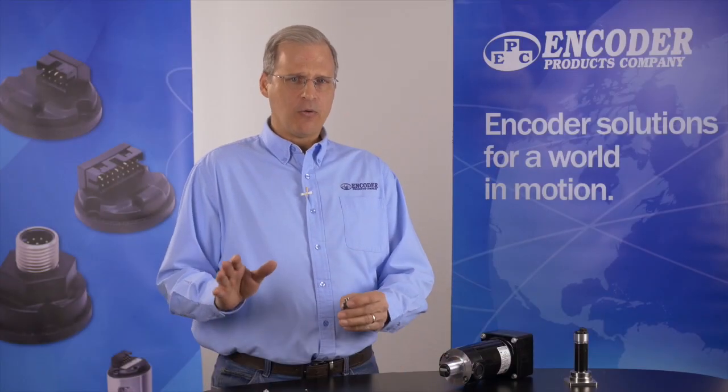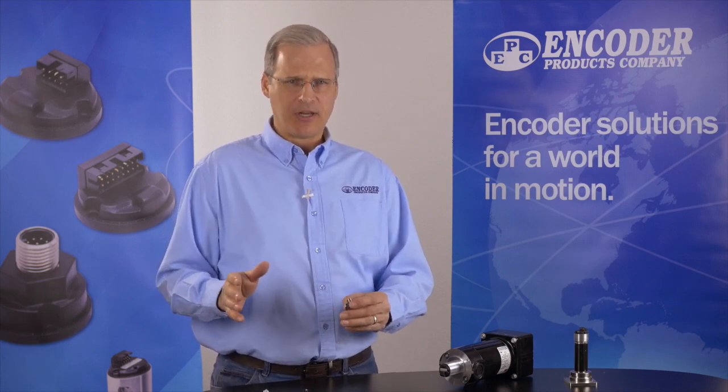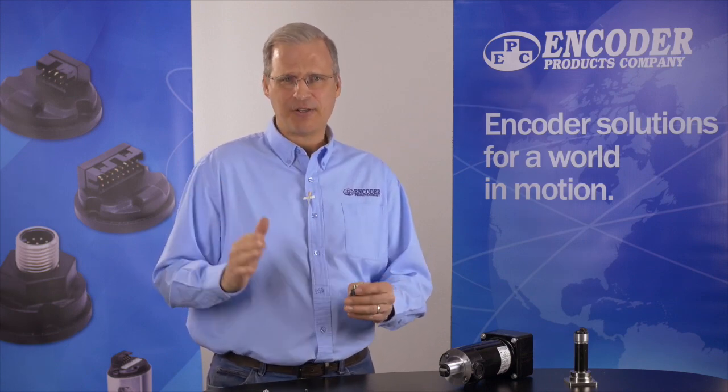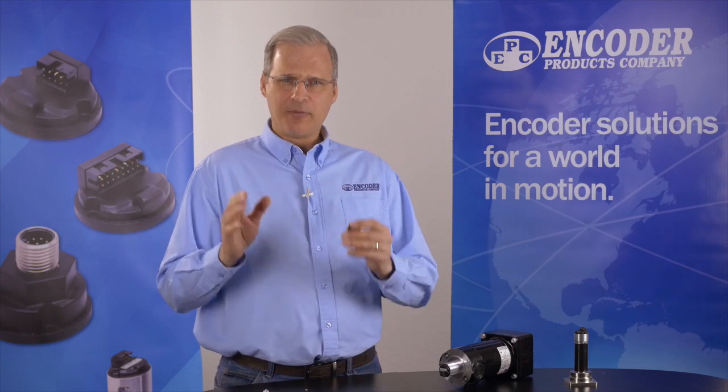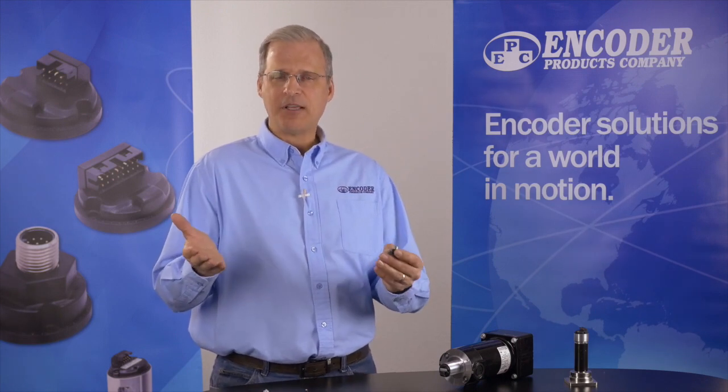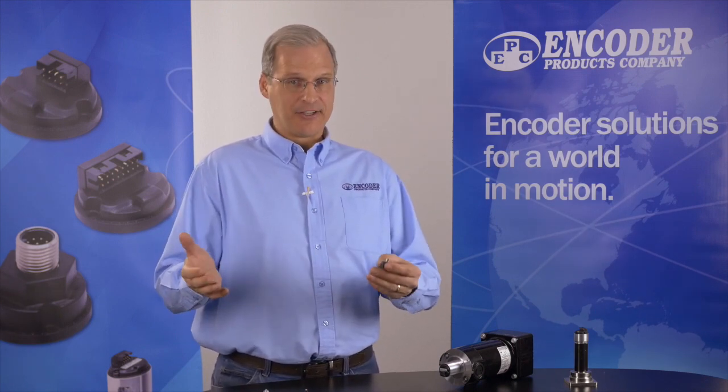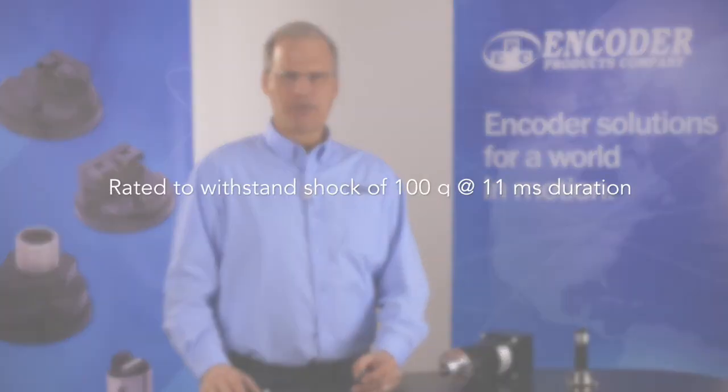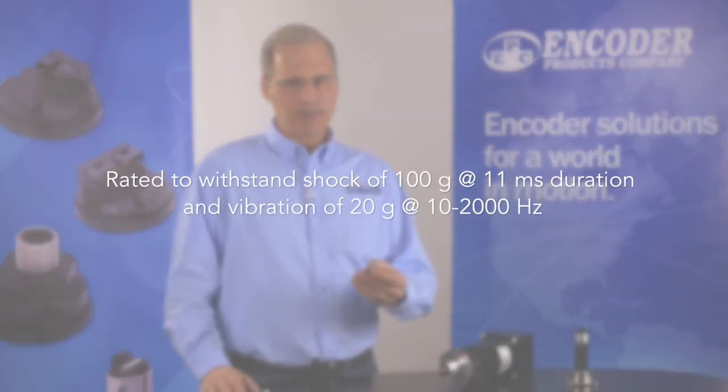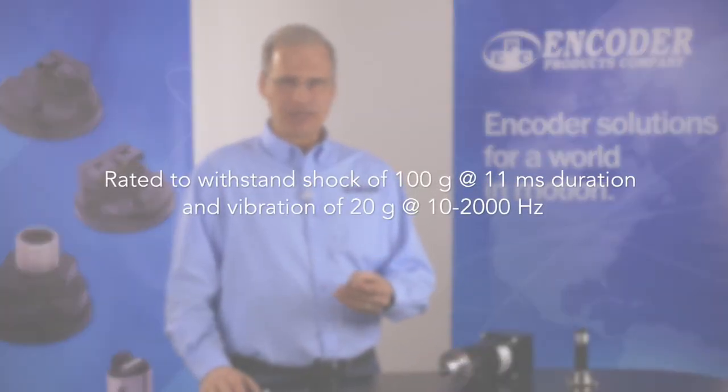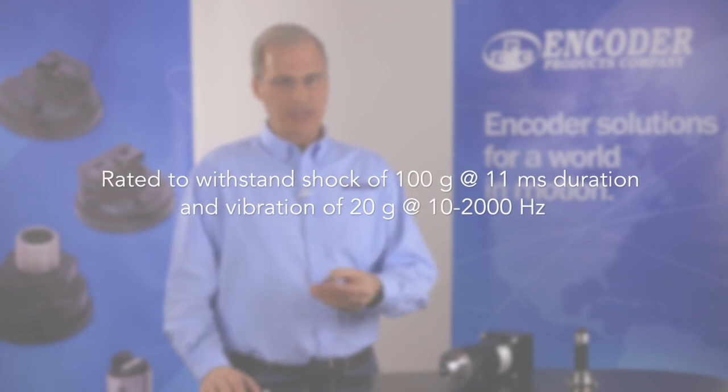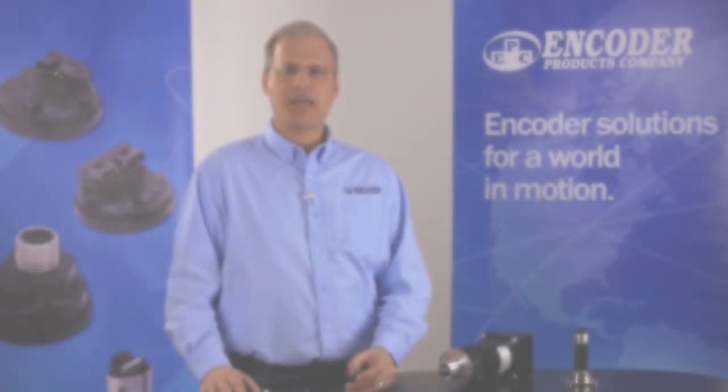Now, with no internal moving parts and a generous air gap tolerance of plus or minus 20 thousandths of an inch, the Model 30M is tolerant of shaft end play, radial runout, and axial offset. It also has a robust shock rating of 100 G's at 11 milliseconds duration and a vibration spec of 20 G's at 10 to 2,000 hertz.